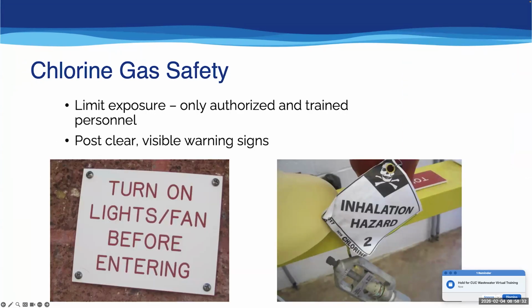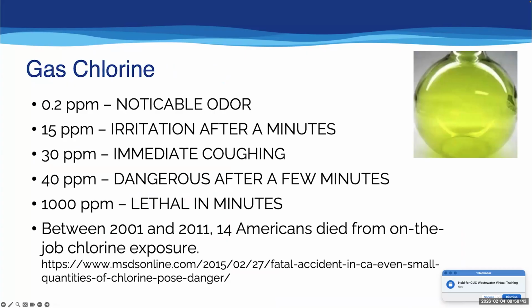Most important thing, limit exposure. Again, only authorized and trained personnel should be anywhere near chlorine gas. You want to have clear visible signs. You want to have trainings. As I mentioned, chlorine has a smell, which fortunately we've got really good noses at 0.2 parts per million. There's a noticeable odor. If you smell that, leave.